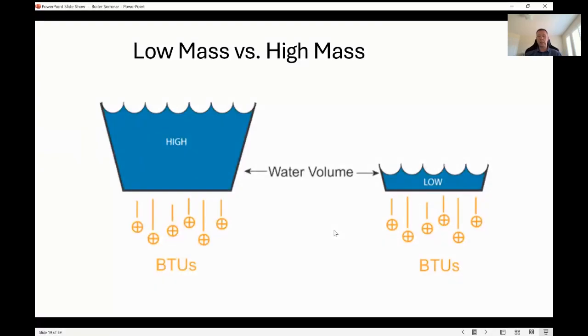You can also take a look here. It's a smaller tube. If you flow that too quickly, it's a small tube, you can erode that tube. That's why they generally have a much narrower flow rate or flow range requirements there. On the left here, you can see the high mass product. If you slow that flow down too much, or quite a bit, there's a lot of water there to absorb those BTUs. You're not just going to flash the steam. And of course, if you speed it up, generally it's not a small tube. You're not going to erode the tubes. You're generally limited by the inlet and outlet connection diameter on that boiler to what your maximum flow rate is on it.